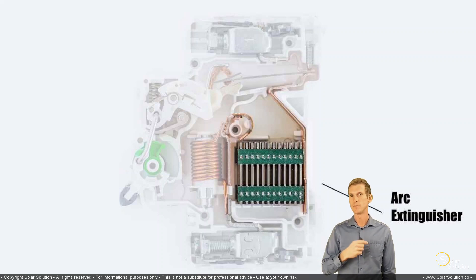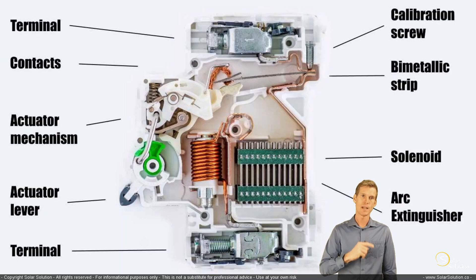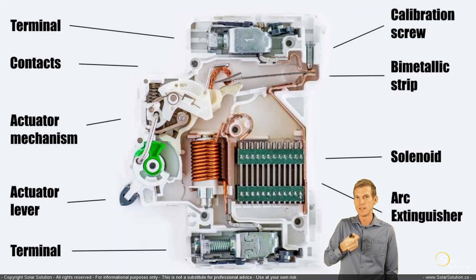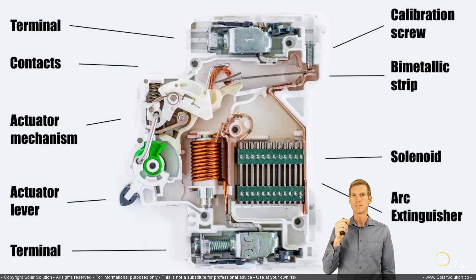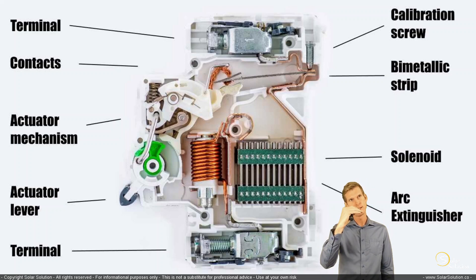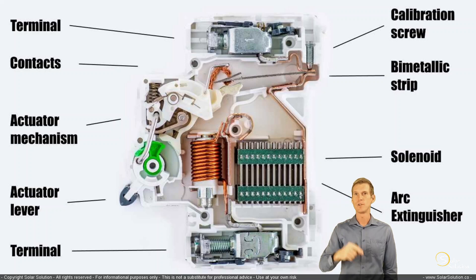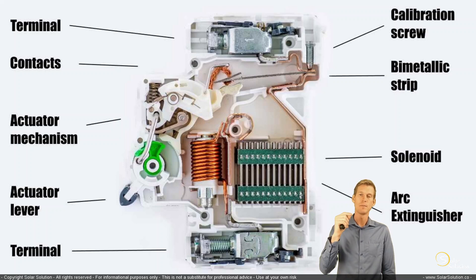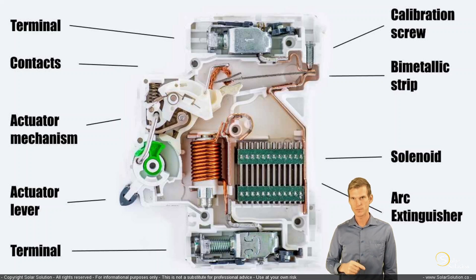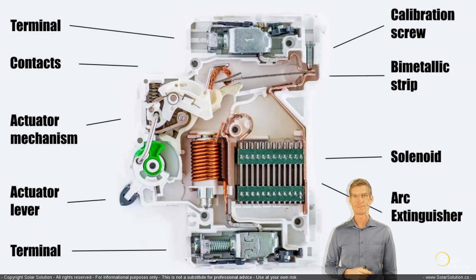So we have a good idea of what's inside the breaker: the terminals for connection, the actuator lever with its mechanism for flipping, the contacts for making or breaking the circuit, the bimetallic strip that bends for the slow tripping current, the calibration screw for fine-tuning, the arc extinguishing chamber, and the solenoid responsible for the instantaneous tripping current.